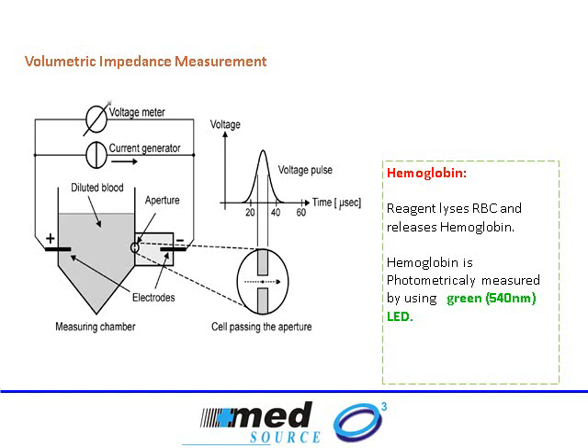By counting the number of times we get a small signal, we know how many platelets we have. By counting the number of times we get a medium signal, we know how many RBCs we have, and by counting the large signals, we know the amount of WBCs. The blood is diluted so that only one cell passes through the aperture at any point in time. Within WBCs, lymphocytes have a different size compared to monocytes and granulocytes, producing different electrical signals. The machine counts all of them and reports the values.